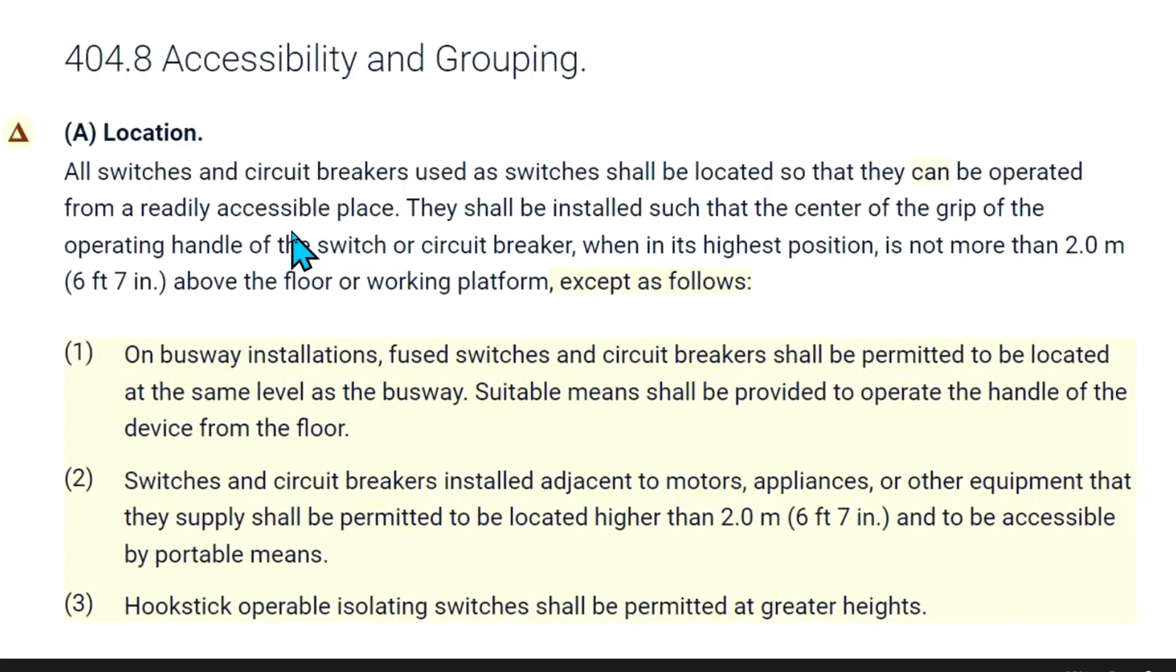A, location: all switches and circuit breakers used as switches shall be located so they can be operated from a readily accessible place. They shall be installed such that the center of the grip of the operating handle of the switch or circuit breaker when in its highest position is not more than 2.0 meters, that's 6 foot 7 inches, above the floor or working platform, except as follows.